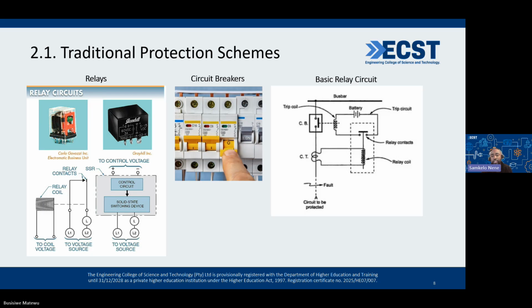If there is no anomaly, then the relay operates as normal. It doesn't send a command. However, if it detects a spike in the incoming current, the relay coil, I hope you see the picture, is energized, which then closes the relay contact as you see in the picture, and then the DC circuit with the battery is energized, which trips the coil for the circuit breaker, and then it breaks the circuit, and then the equipment is protected.